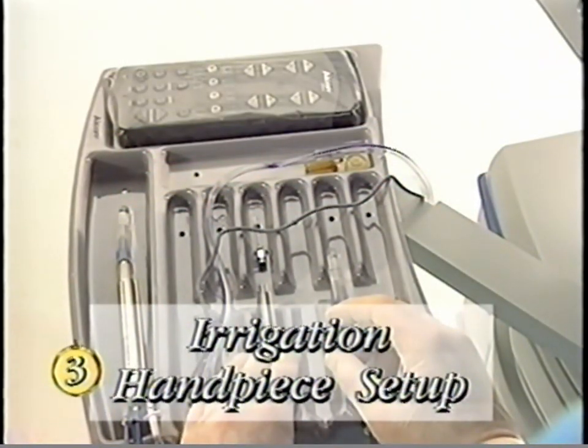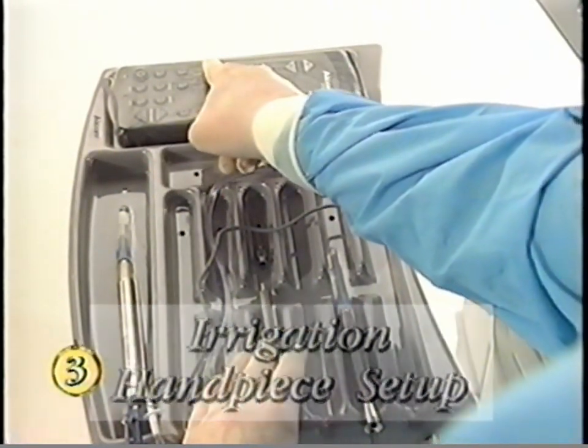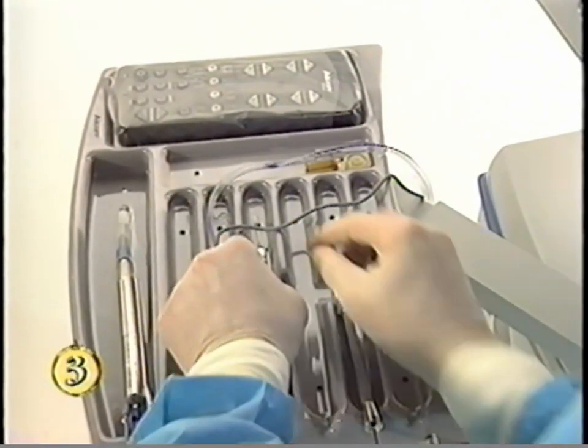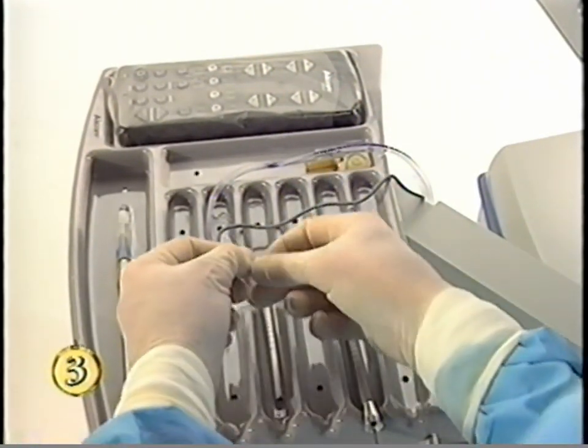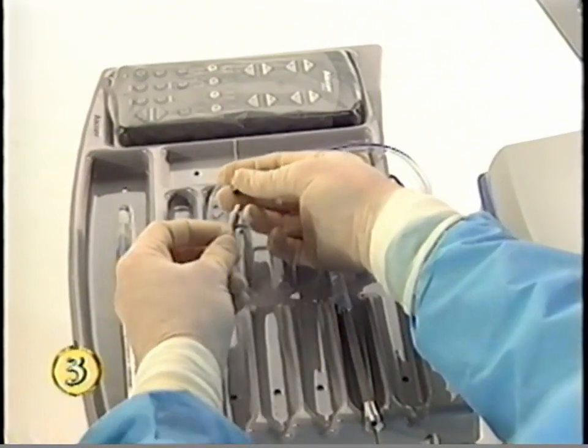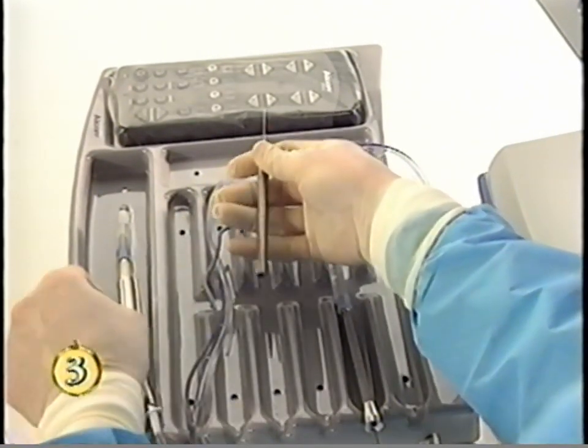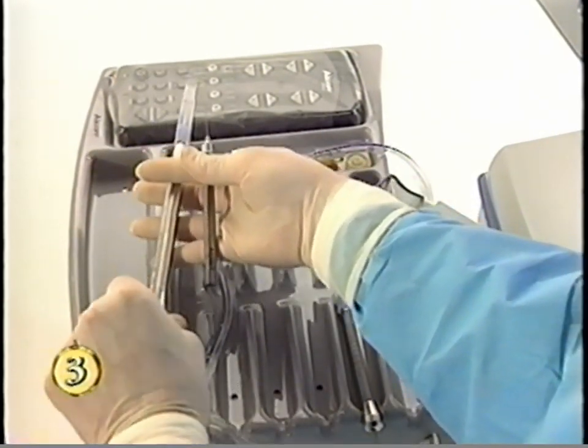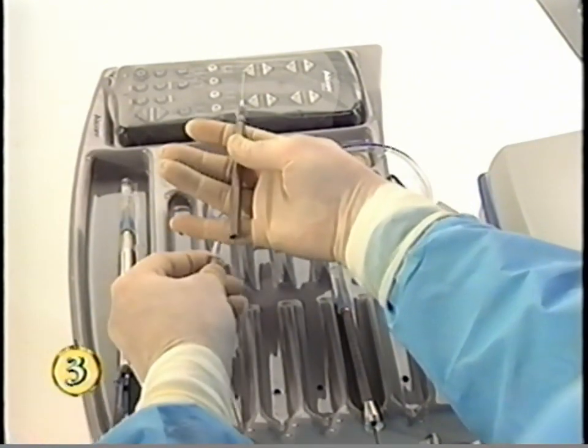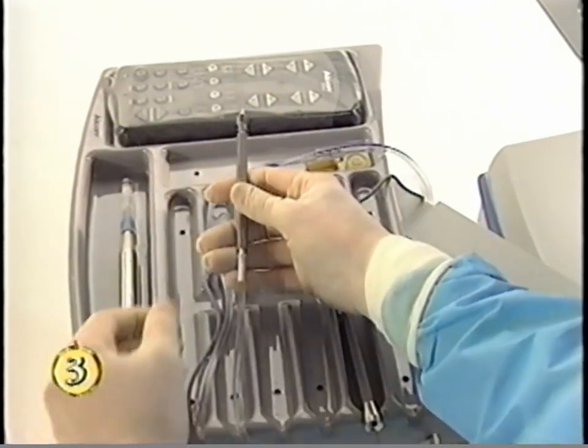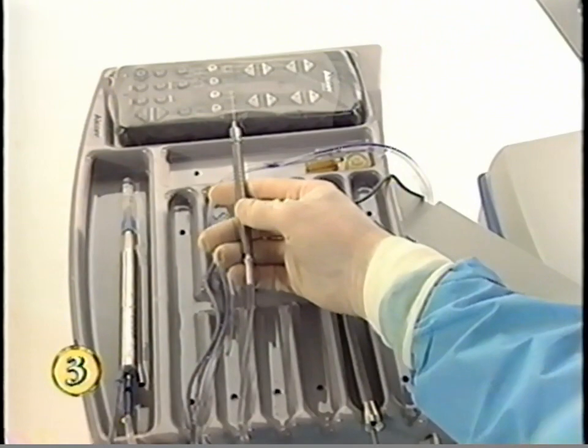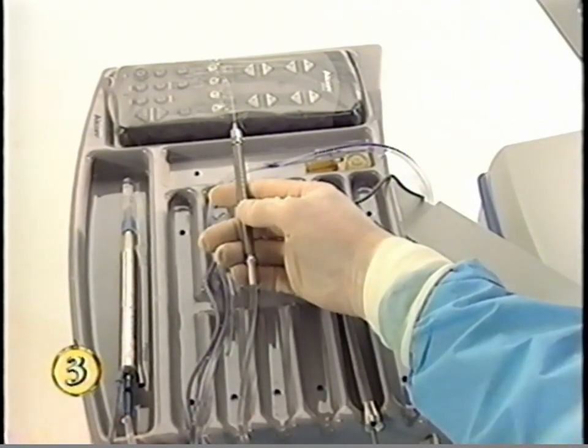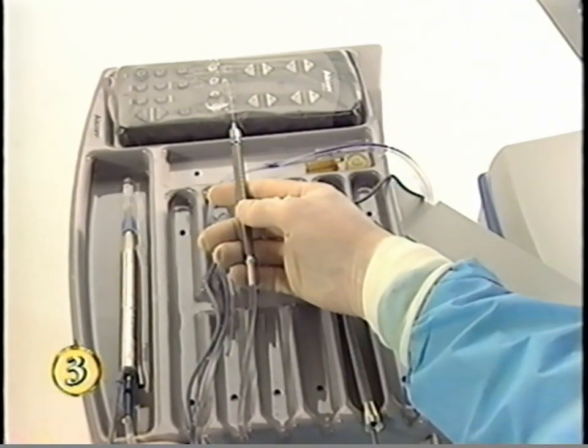To set up the irrigation handpiece for surgery, press the irrigation mode selection key. Select the irrigating tip and attach it to the irrigation handpiece. Remove the irrigation tubing from the ultrasound handpiece and connect it to the irrigation handpiece. To prime the handpiece, depress the foot switch to position 1 for several seconds or use irrigation free flow. Always prime the irrigation handpiece in irrigation mode.